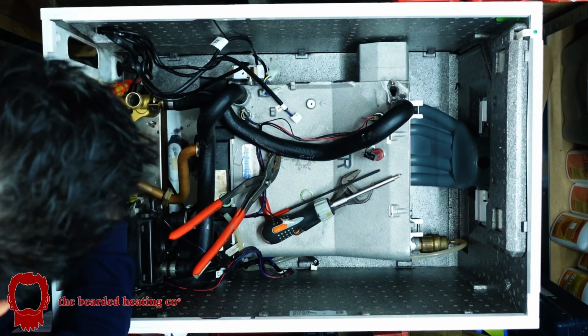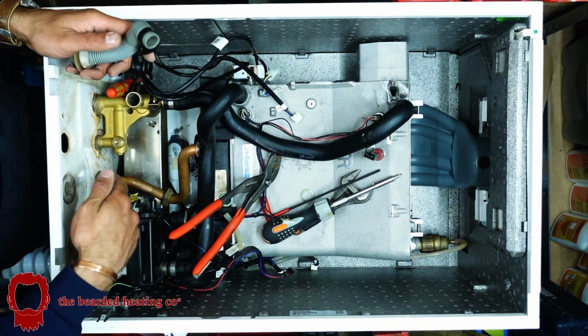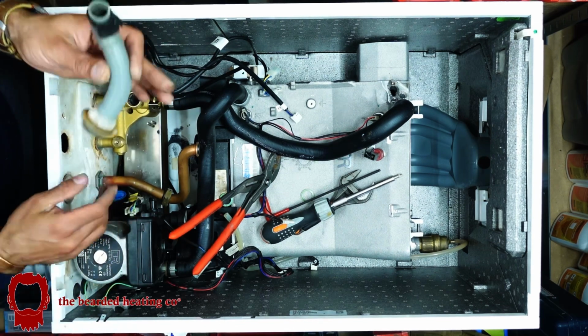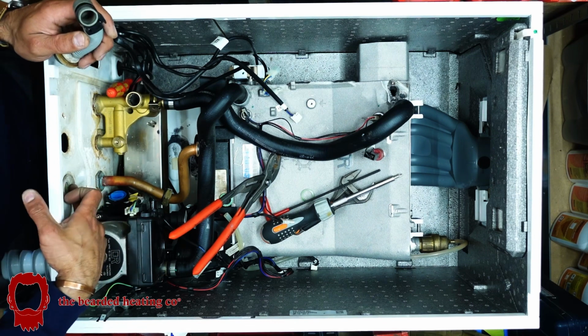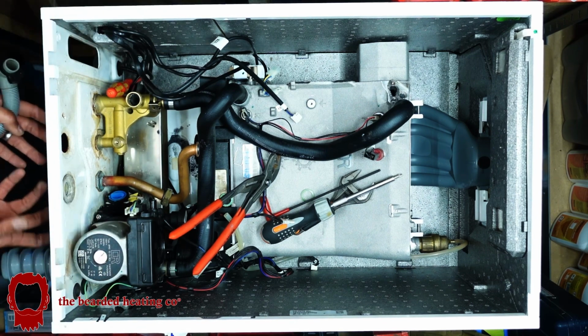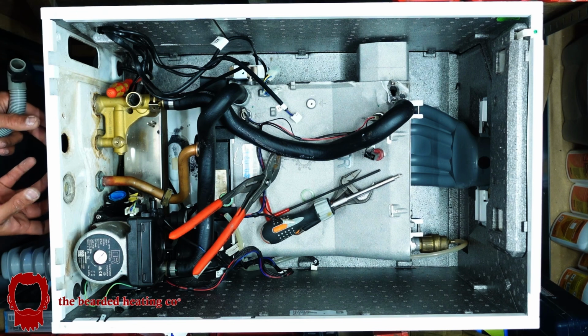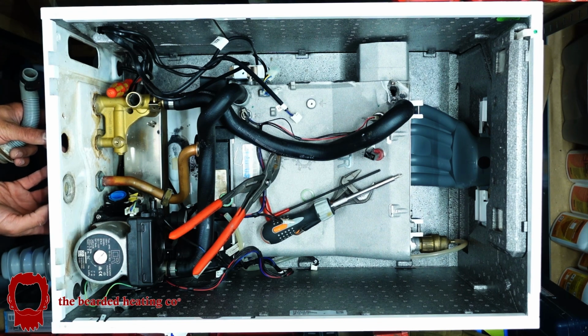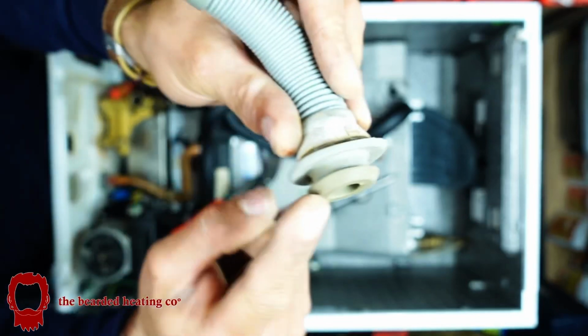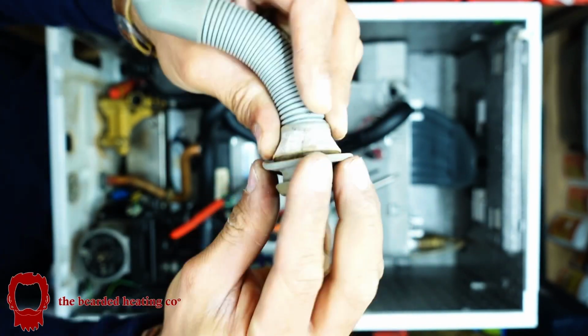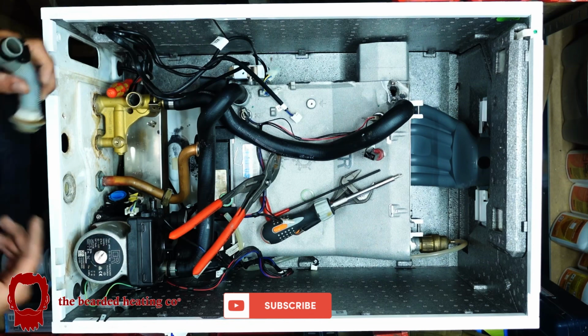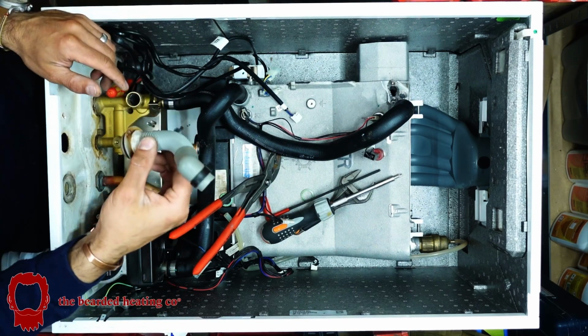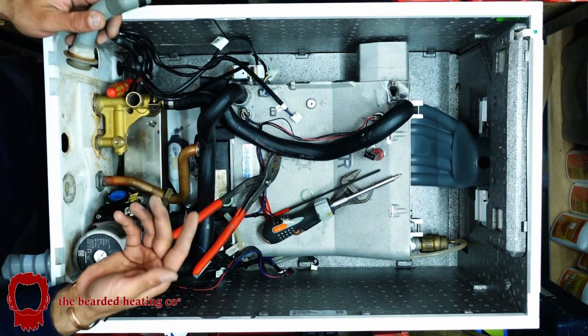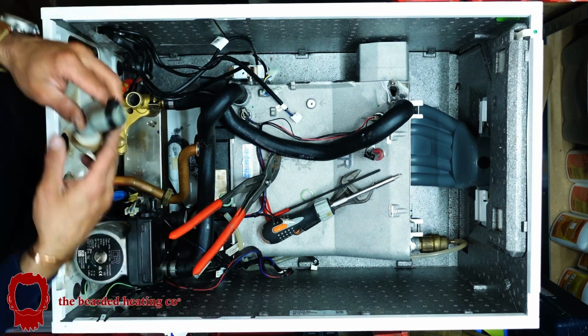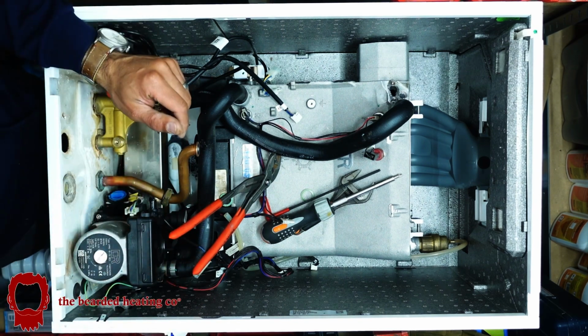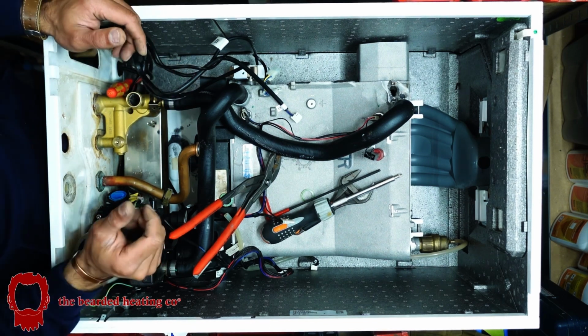The nice thing about this boiler, which I haven't discussed yet: at the bottom here you can see two rubber grommets, one for the PRV and one for the condense. Underneath, which I don't have with me, is a rubber housing that clamps on, because the actual grommet has this lug. It clips onto the lug here and holds in place so the condense and the PRV are combined. Less work for the installer. I do like that design. That's great, so I'll keep that just in case it's ever split on the job.